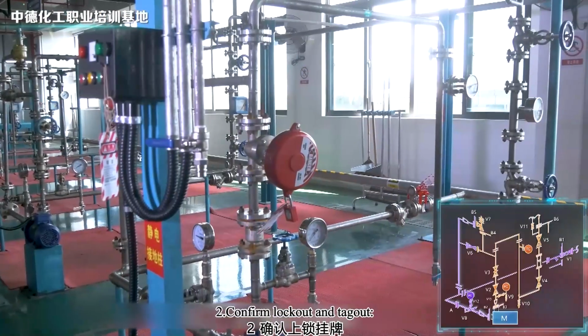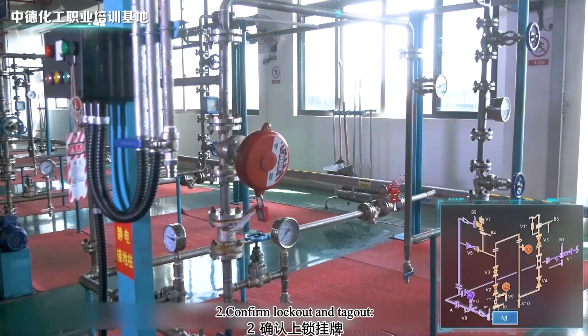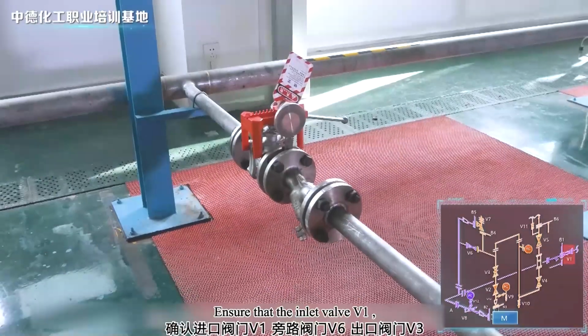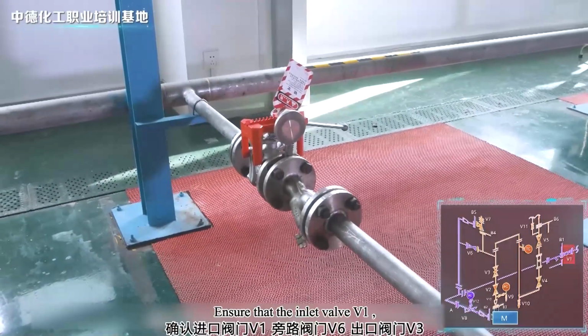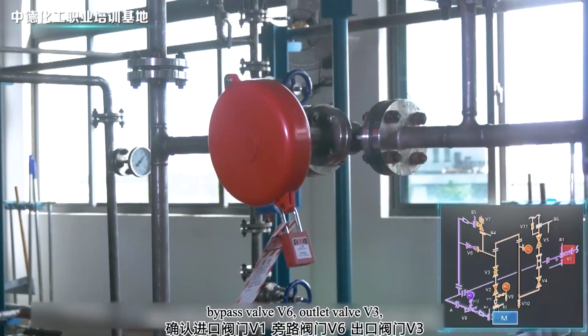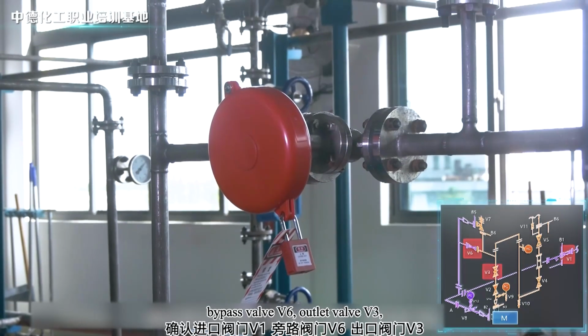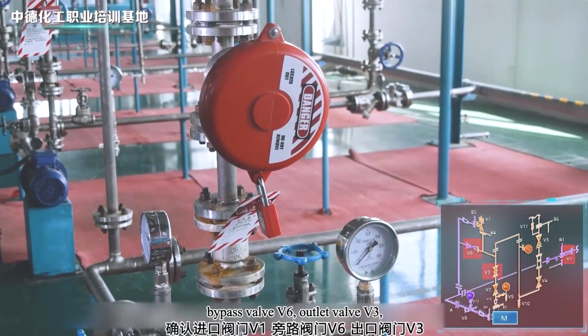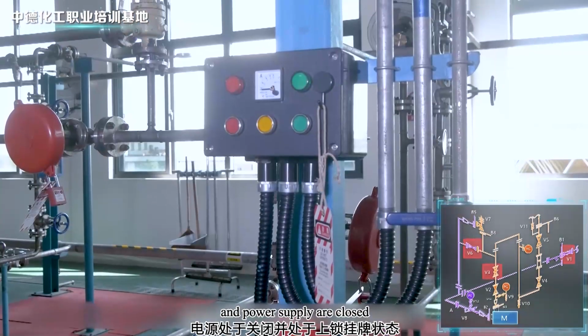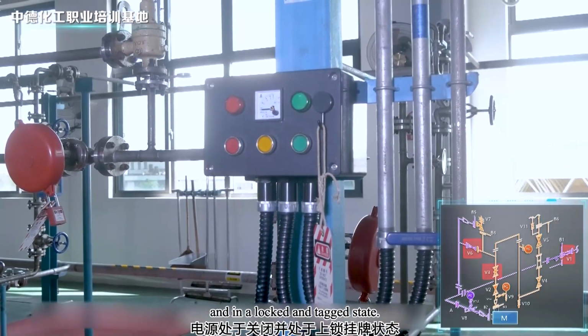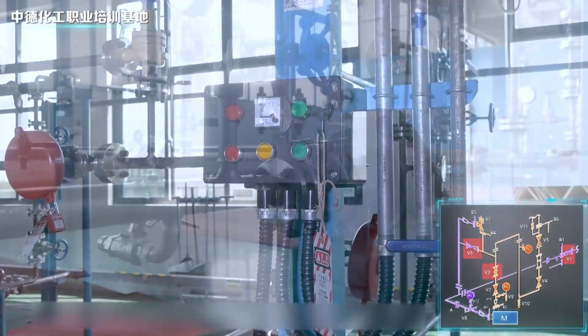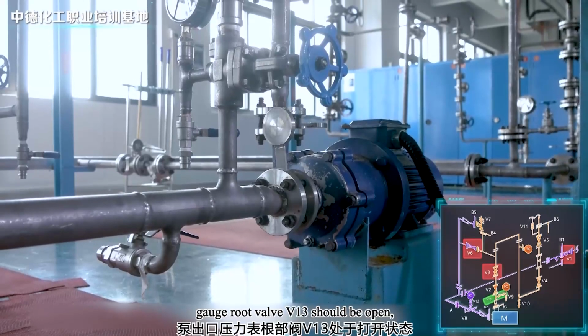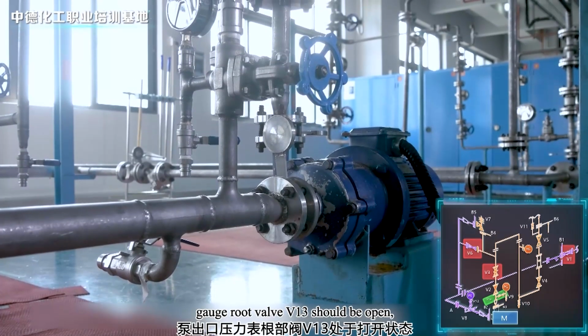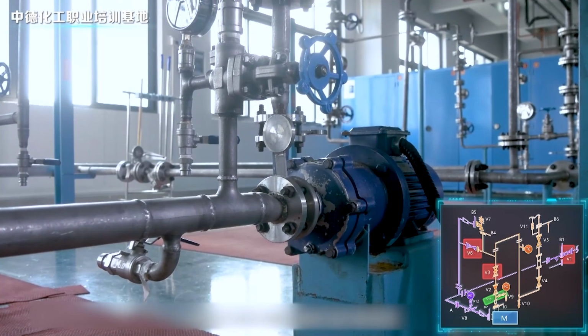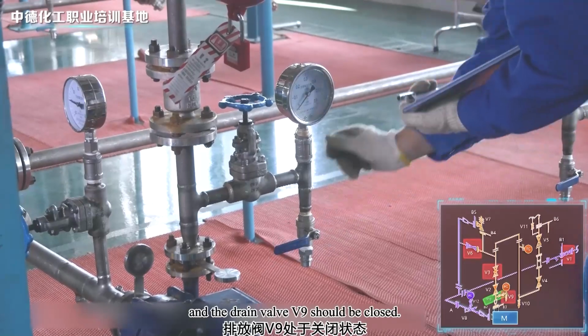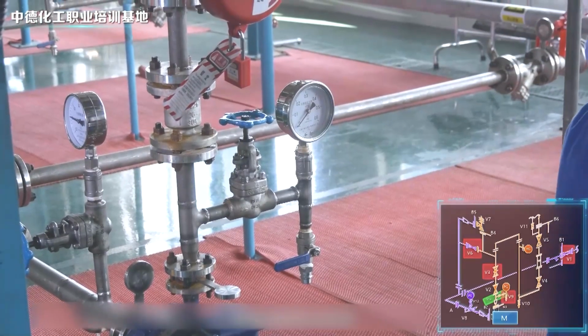Second, confirm lockout and tag out. Ensure that the inlet valve V1, bypass valve V6, outlet valve V3, and power supply are closed and in a locked and tagged state. The pump outlet pressure gauge root valve V13 should be open, and the drain valve V9 should be closed.